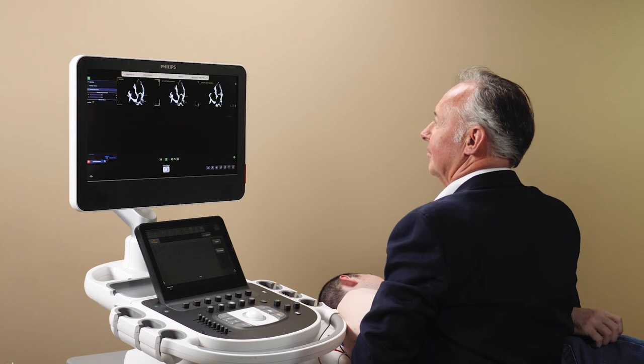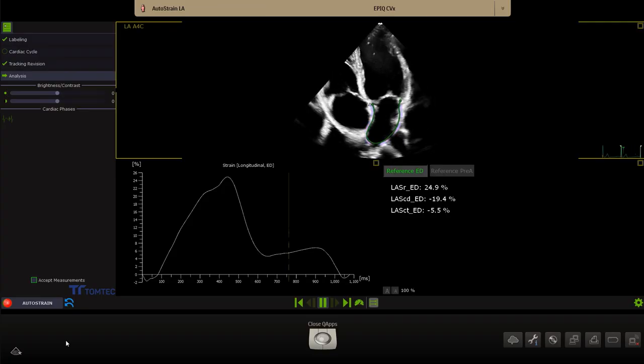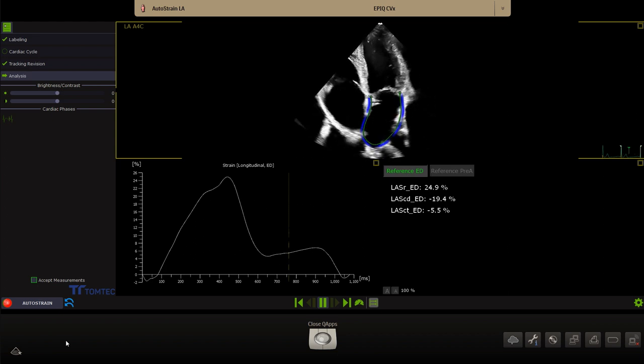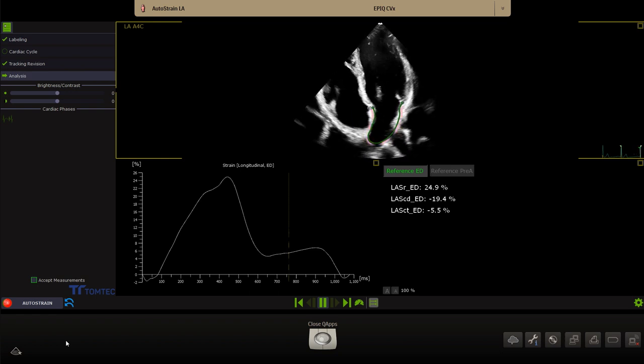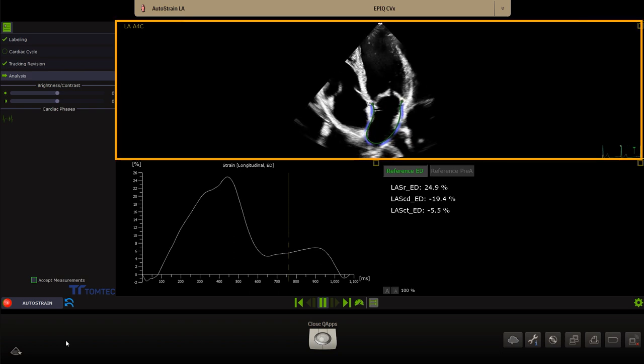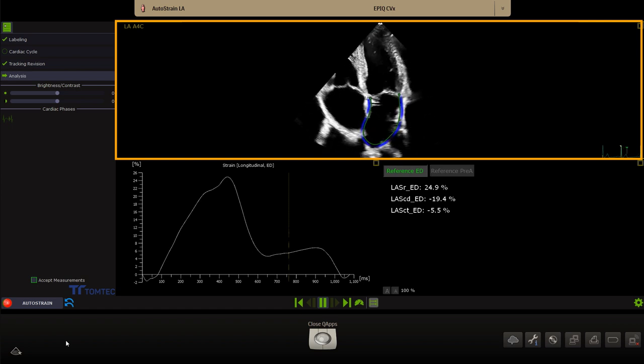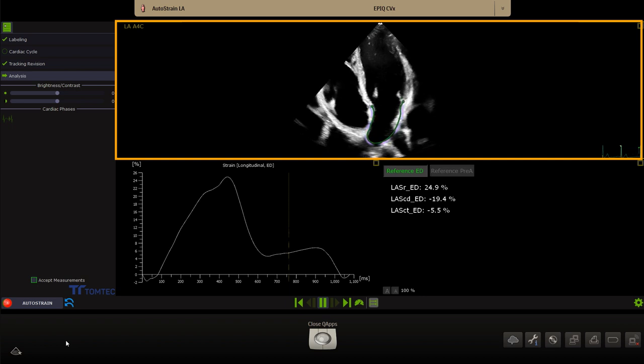The one button push AUTOSTRAIN LA provides a fast and reproducible longitudinal strain measurement of the left atrium. The AUTOVIEW recognition and ROI placement algorithm automatically assigns the view label and places the contour of the left atrium. The AUTOVIEW recognition and tracking can be reviewed on the dynamic 2D loop.